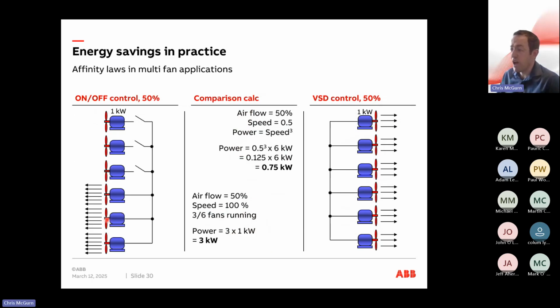This is another example with some fans. Some fans are using on-off control 50% of the time, others using VSD control 50% of the time. So with the on-off control, you have 6 fans, you're switching off 3 of them, and 3 of them are running at 100% load. With the VSD control, you have 6 fans running, but they're all running at 50% load.